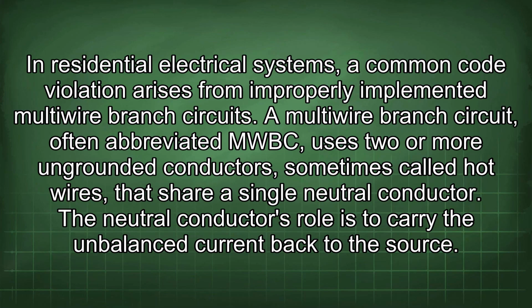In residential electrical systems, a common code violation arises from improperly implemented multi-wire branch circuits. A multi-wire branch circuit, often abbreviated MWBC, uses two or more ungrounded conductors, sometimes called hot wires, that share a single neutral conductor. The neutral conductor's role is to carry the unbalanced current back to the source.